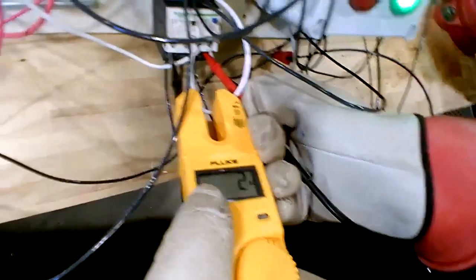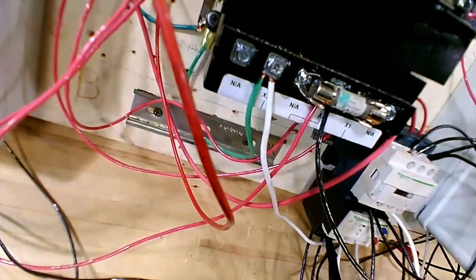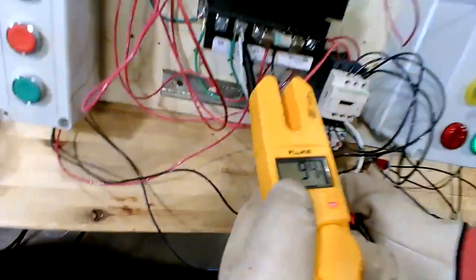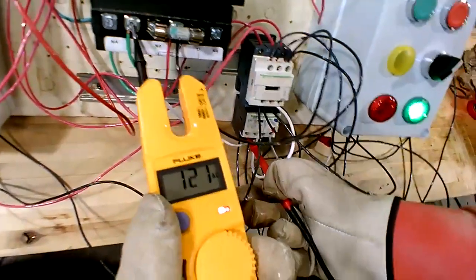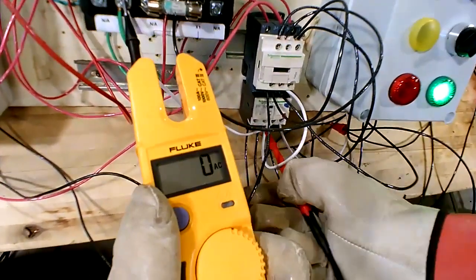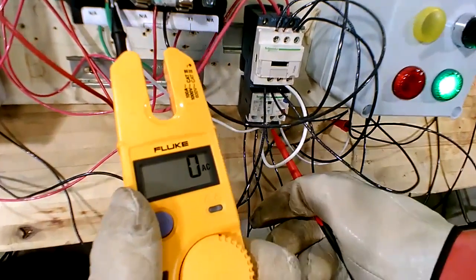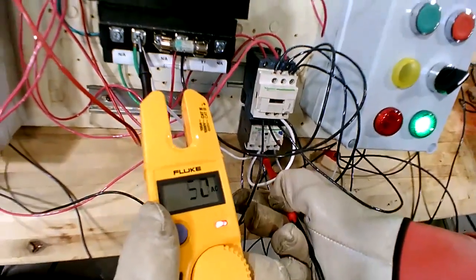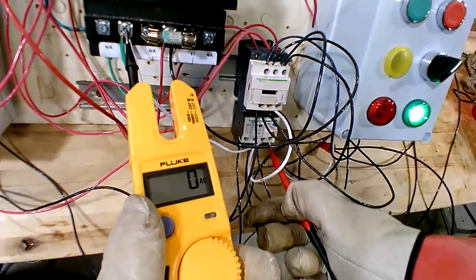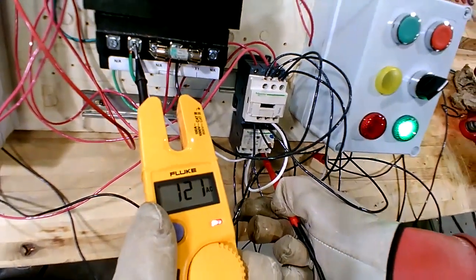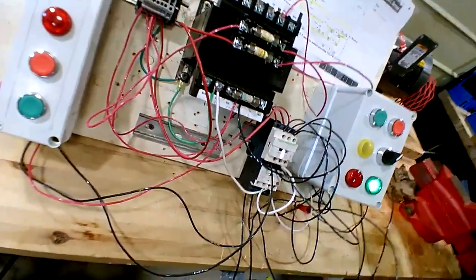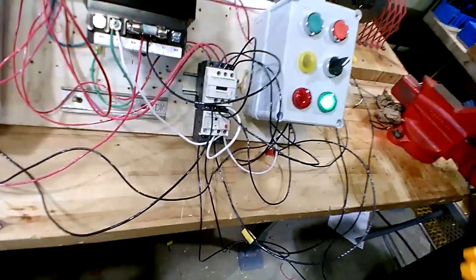You can take your left hand and use this ground up here, your left hand, that way you don't have to cross over. Now that's checking 1 to ground, now 2 to ground. Good, and now 3 to ground. Perfect. That's exactly right when you have a system that's anywhere between 208 and 240. That's what you'll get. Now let's check the amps.